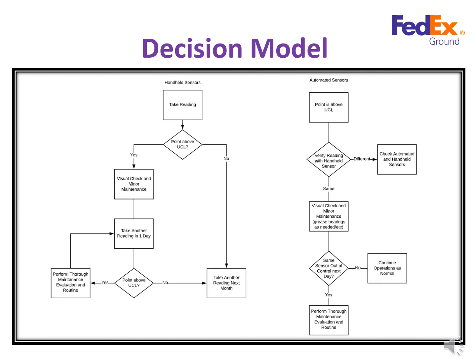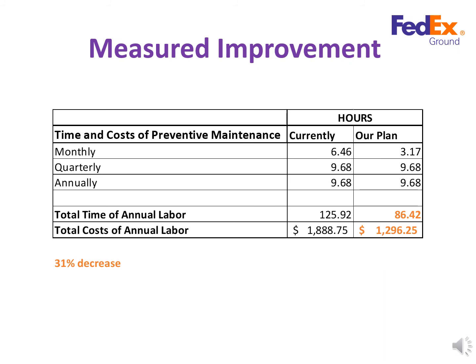If there are no points above the upper control limit for the automated sensors, we continue operations as normal, and for the handheld scanners, we wait to conduct our next set of inspections next month. It is important to note that in the automated sensor decision tree, the handheld scanner is used as a method of verification for the automated sensor reading. Based on our analysis, we believe that continuing to use sensors to monitor the status of the equipment allows a decrease in preventive maintenance tasks.